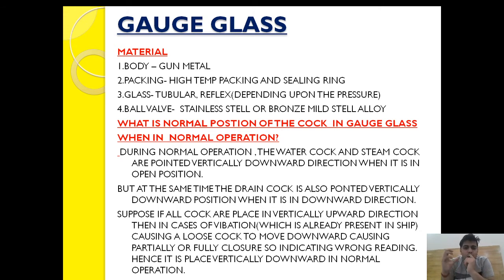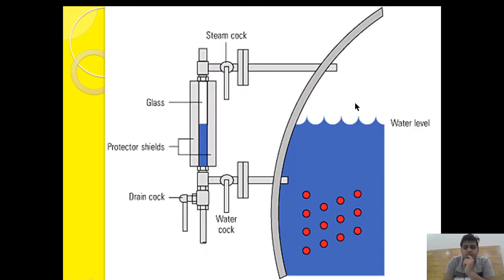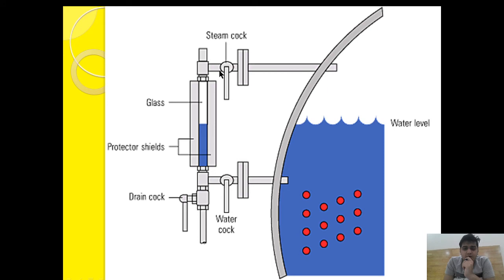The second question asked in MU Class 4 is: what is the normal position of the cock in the gauge glass during normal operation? When the boiler is in normal working condition, what should be the position of the cock and why? As you can see, this is a tubular type gauge glass. There are three cocks — steam cock, water cock, and drain cock — and all three are shown pointing in a vertical downward direction. The steam cock and water cock in vertical downward position are in open condition.